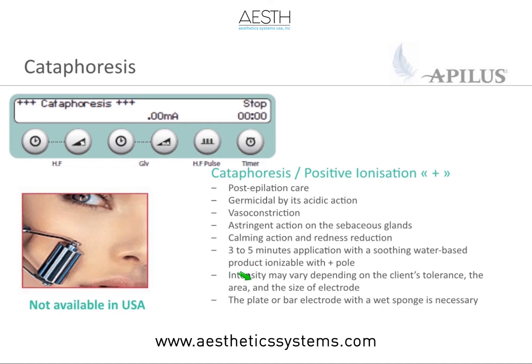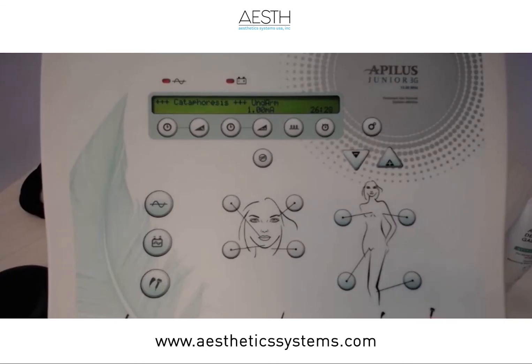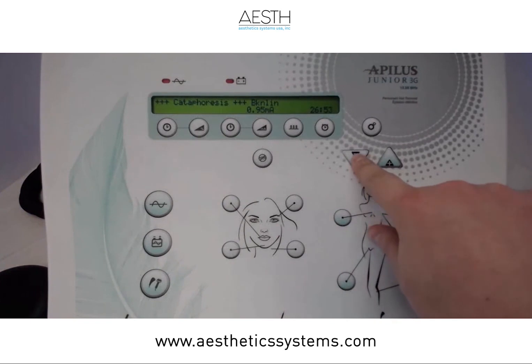You can always use your plus and minus, your arrows on the screen, in order to move the preset up and down. What I would say is, be careful not to press on the foot pedal when you are performing cataphoresis, because pressing on the foot pedal increases the setting. So some people think they have to press on the foot pedal in order for this to work. If you do that, you're going to be maxing out the mA every single time, and then it will hurt every single time. So don't press on the foot pedal. Just pick a preset and then adjust using the plus and the minus if you need to.